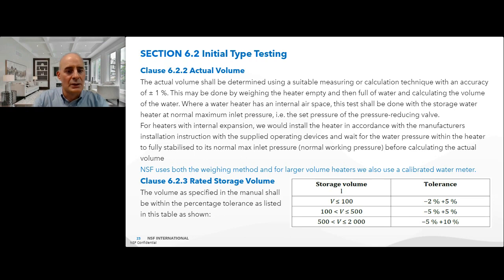For heaters with internal expansion, we would install the heater in accordance with the manufacturer's installation instructions with the supplied operating device and wait for the water pressure within the heater to fully stabilize to its normal maximum inlet pressure, so the normal working pressure, before calculating the actual volume. NSF uses both the weighing method, and for larger volume heaters, we also use a calibrated water meter.